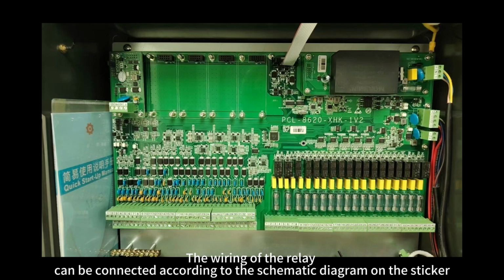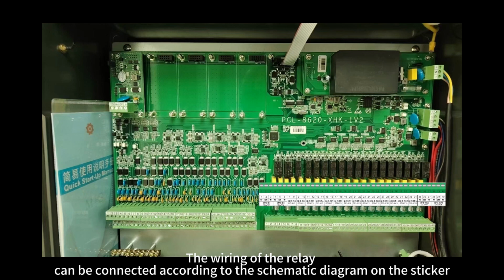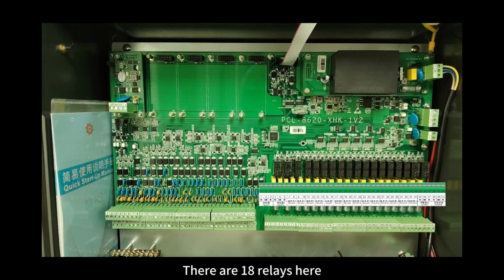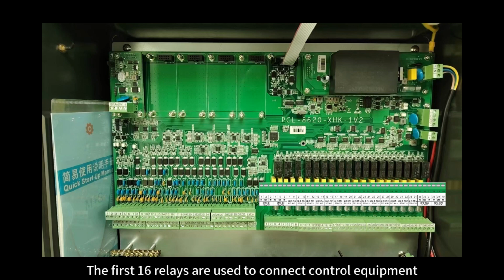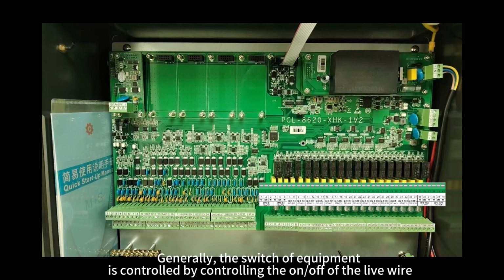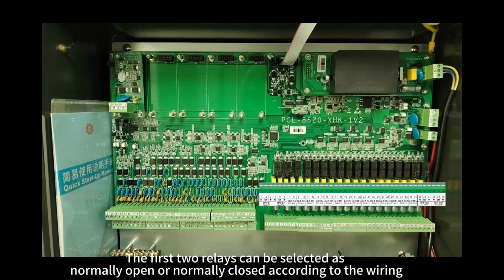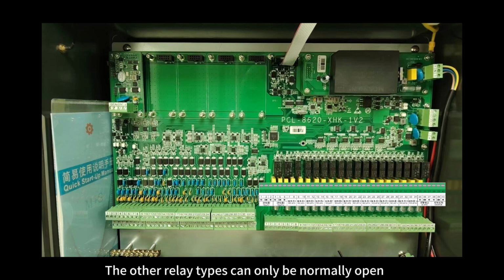The wiring of the relay can be connected according to the schematic diagram on the sticker. There are 18 relays here. The first 16 relays are used to connect control equipment. Generally, the switch of equipment is controlled by controlling the on-off of the live wire. The first 2 relays can be selected as normally open or normally closed according to the wiring. The other relay types can only be normally open.